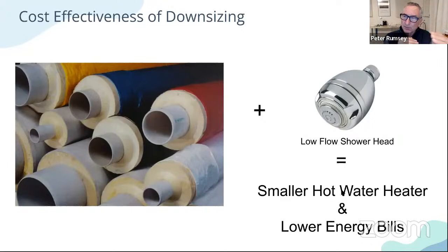So we like to invest in the passive elements, like insulation and better glass, so that our active equipment, our cooling equipment or water heating equipment, can be smaller, simpler, and lower cost. When we invest in the passive, we're lowering the loads on the active. That's a very fundamental thing to remember, a very powerful way of looking at buildings. Many professionals I work with, once they get that, it changes the way they think about design.